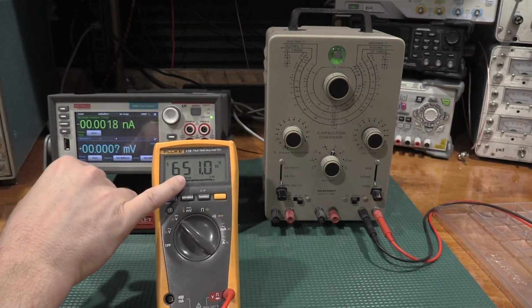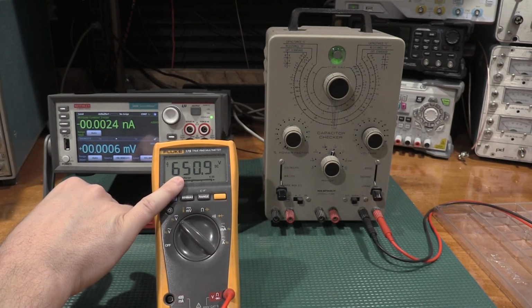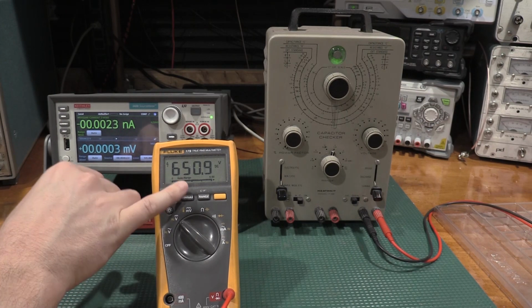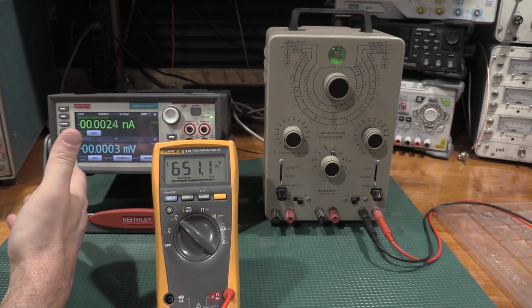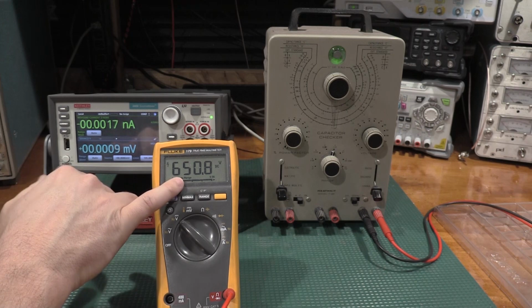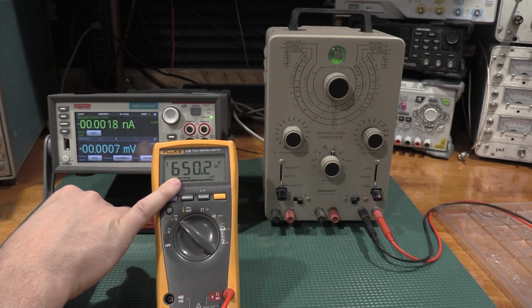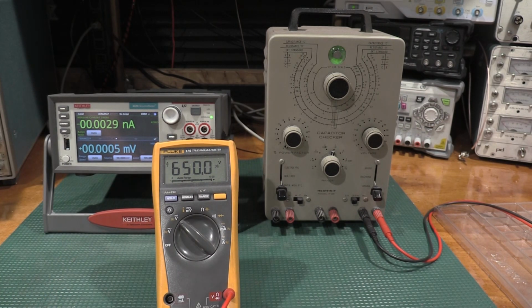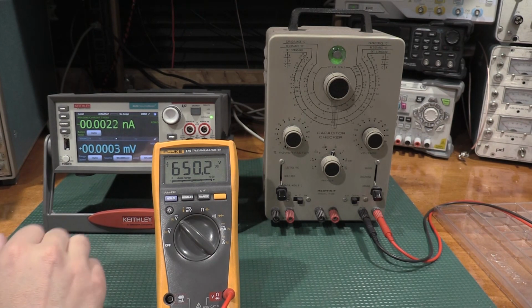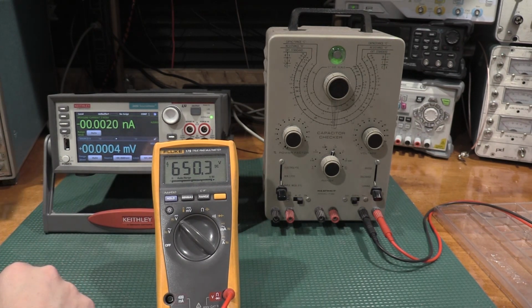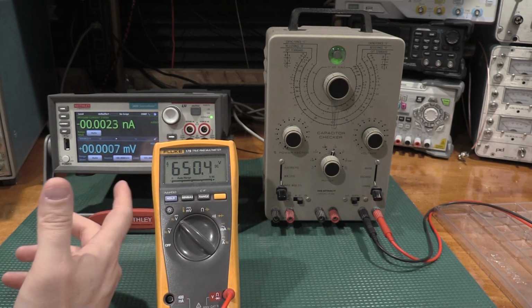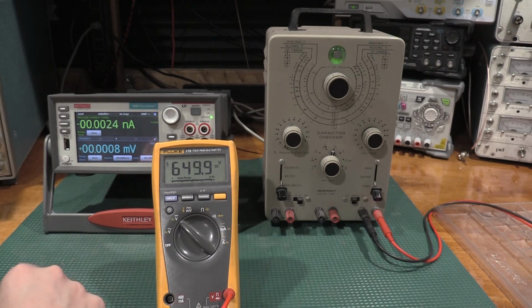I'm supposed to be at 600, but because of the error in line voltage, we're at 650 volts. So if you try to test a 600 volt modern cap there, absolutely this is going to do some damage to that capacitor. It's going to overheat it and cause it to draw heavy current and make it not have a good day. So just something to be aware of. This can be adjusted with a variac, bring it down a little bit or not.